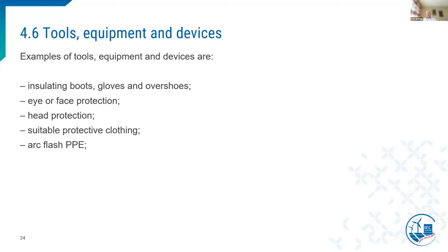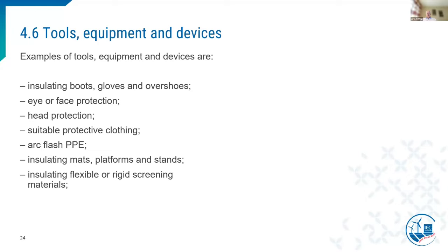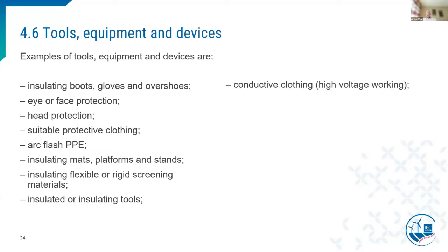Arc flash PPE, insulating mats, platforms, and stands in case of live working, insulating flexible or rigid screening materials also for live working, insulating tools, conductive clothing - this is only for very high voltage working on overhead lines, operating sticks and rods.